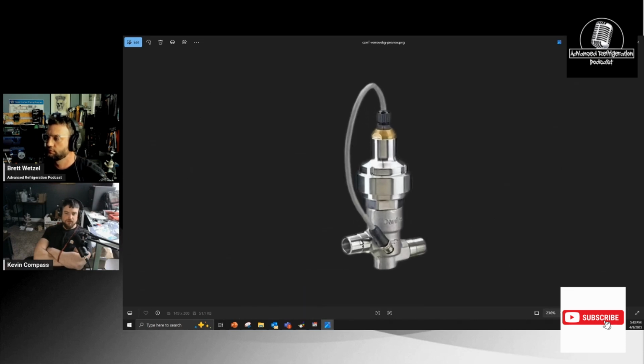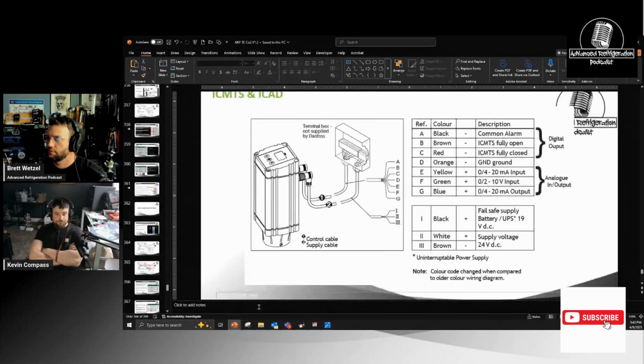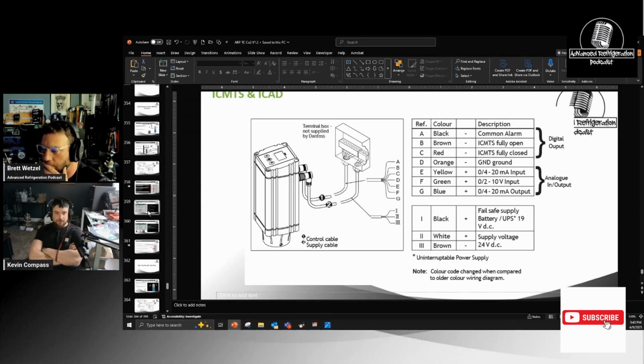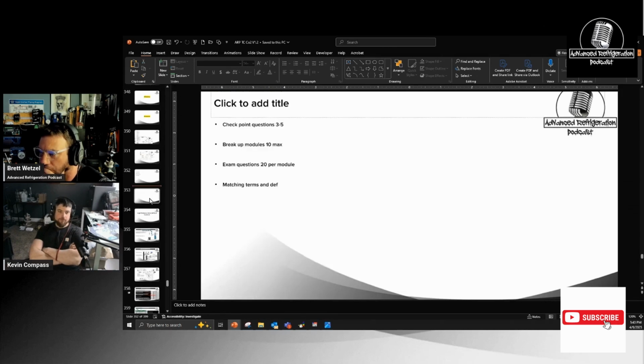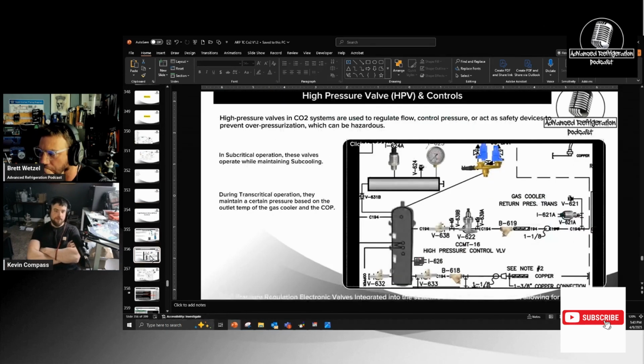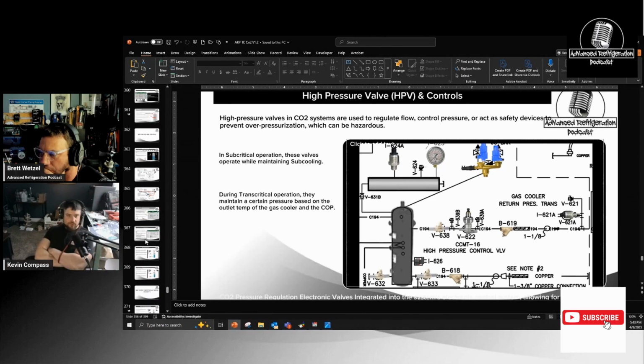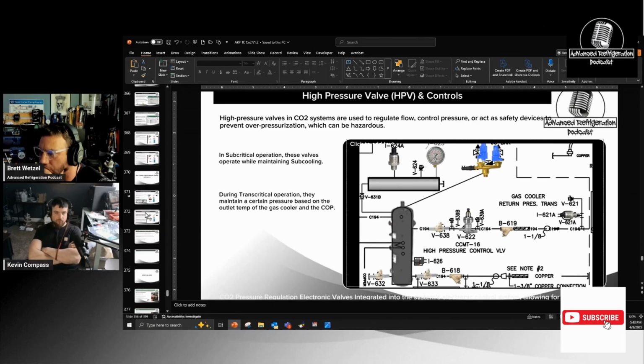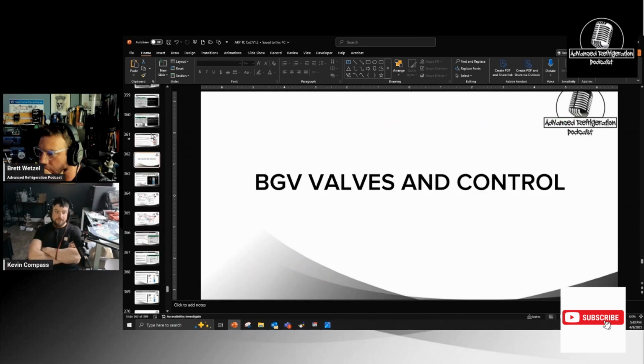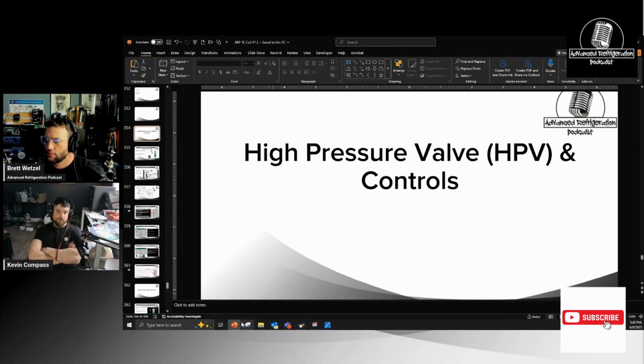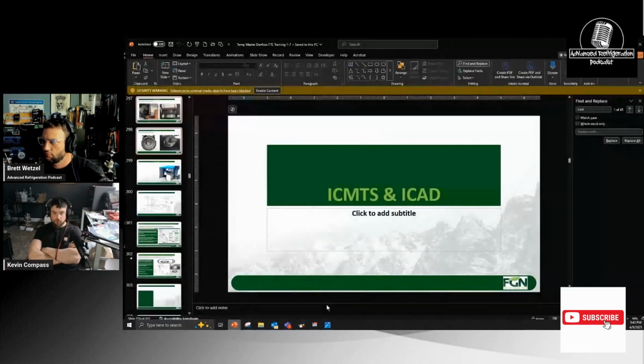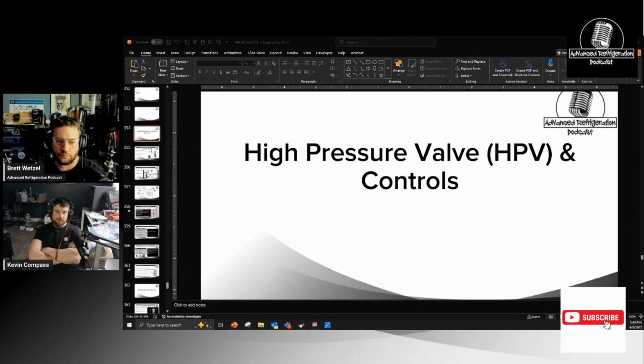Oh, it may be a CCM. No, it's a CCM. Yeah, it is. So that's a CCM valve, and the CCMT's got the tap on it. Now, you'll notice it has the M12 pigtail coming off of it, and we had a couple stores where they shipped out with the wrong pigtails. If you're replacing a Copeland CV valve with a CCMT valve, the M12 connectors will meet up, but they are pinned out differently. Same with the Sporlan ones. You could use a Sporlan pigtail connector on there, but it is pinned out differently.